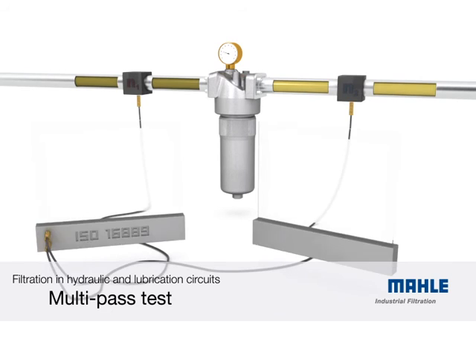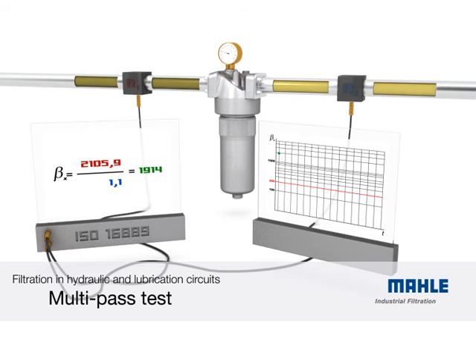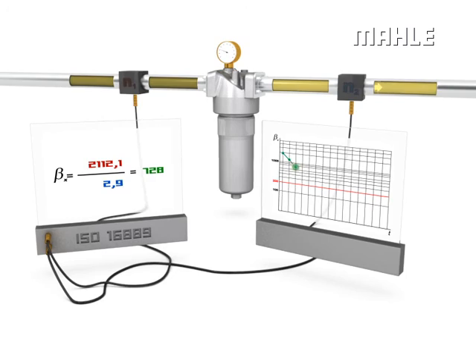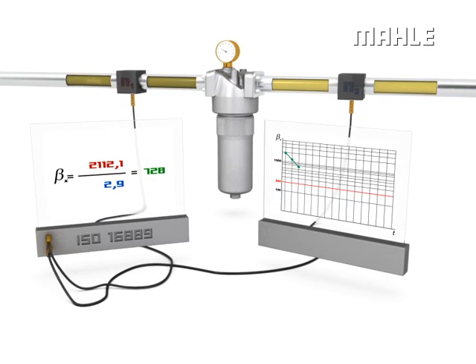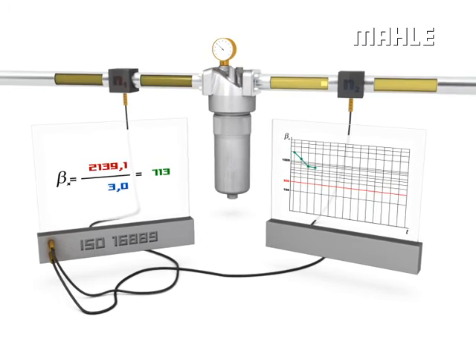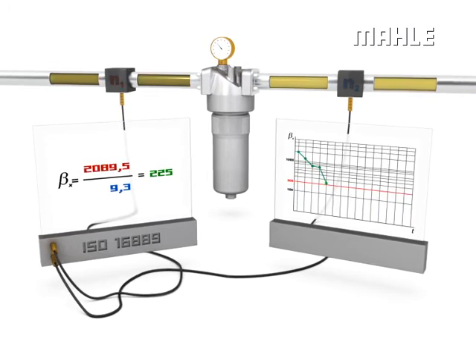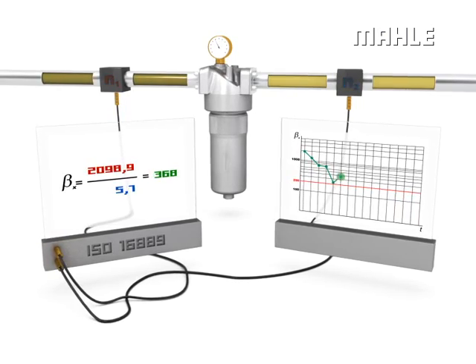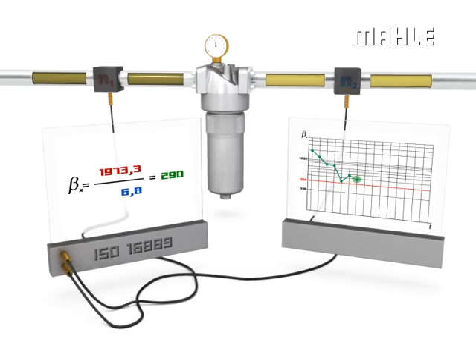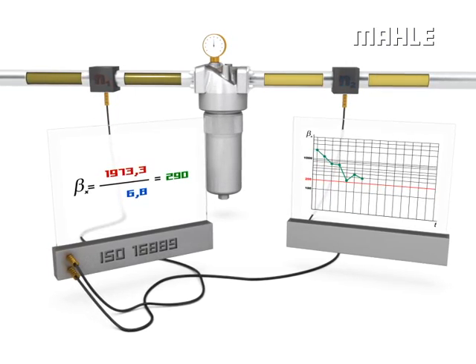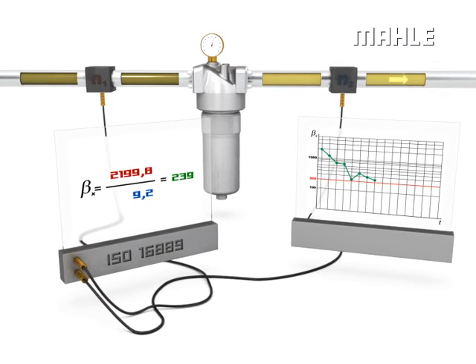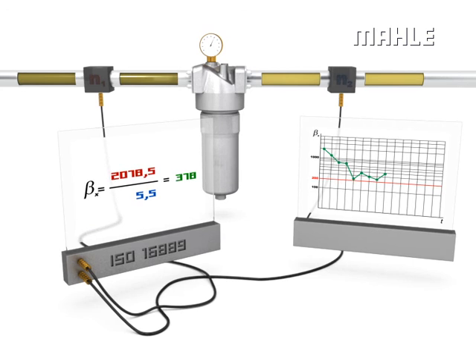The ISO 16889 multi-pass test determines the filtration performance of a filter element and its apparent dirt holding capacity in a closed circuit. The testing liquid is contaminated according to definitions before the test filtration. As the filter separates the test dust, the differential pressure increases across the filter element. Throughout the test, particle counts are taken both upstream and downstream of the filter element, and a beta ratio is calculated based on these values.